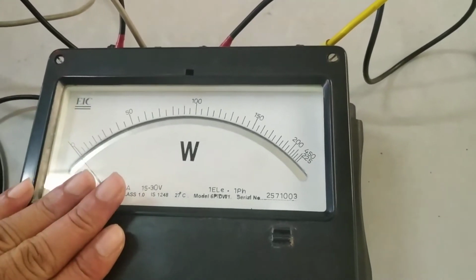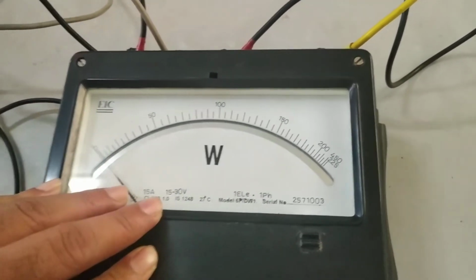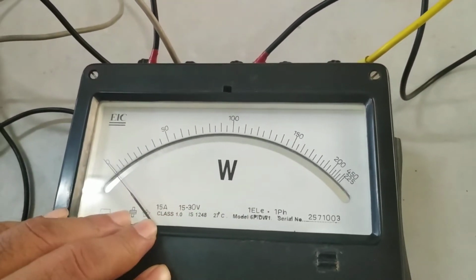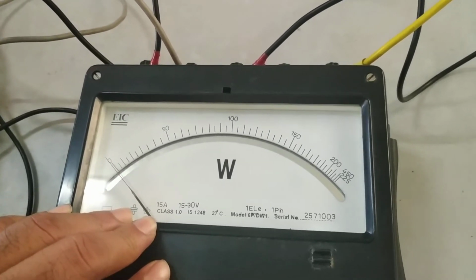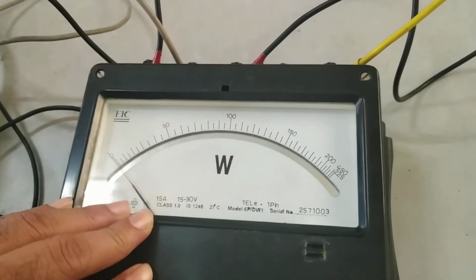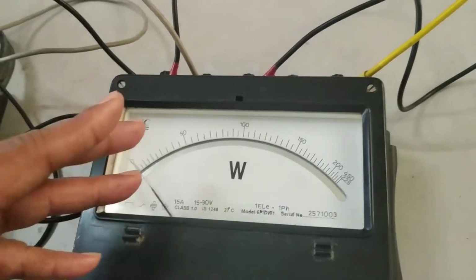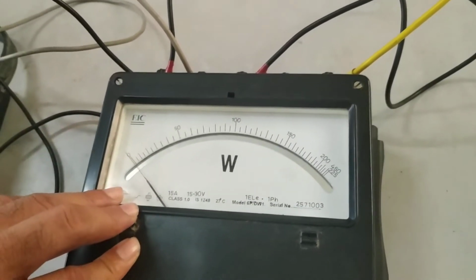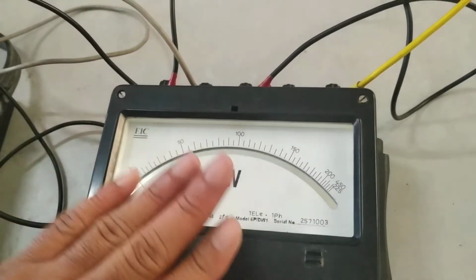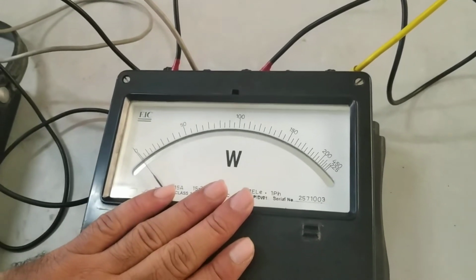This is a unity power factor wattmeter, UPF meter, because during the short circuit the maximum amount of current is flowing in the circuit, that is nothing but the rated current of the transformer, so we should have a unity power factor wattmeter.